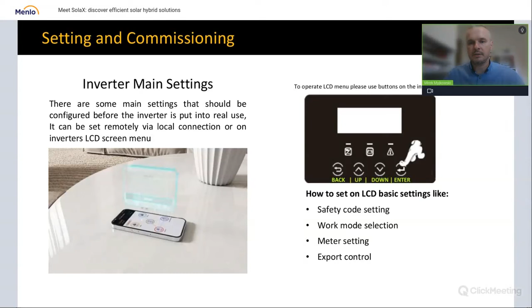And of course, you have to check the meter or CT settings, because if you've installed the meter, you have to set the inverter to work with the meter in the inverter menu. You can also set the export control, which is necessary in many countries, so it's important to know how to do that correctly.